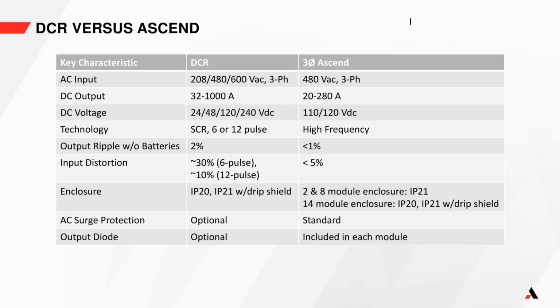The technology on the DCR is SCR based. We either have a 12 pulse or 6 pulse charger, whereas the Ascend is a high frequency charger that has internal modular power supplies. On the DCR without batteries, the output ripple is about 2%, and we're less than 1% on the Ascend. The input distortion on the 6 pulse was 30%, on the 12 pulse 10% for the DCR, and then we're less than 5% on the Ascend.